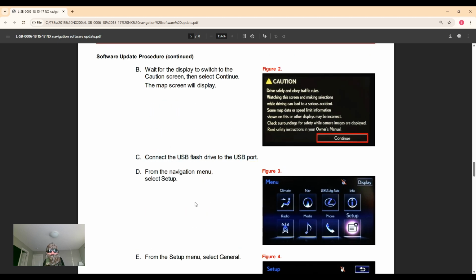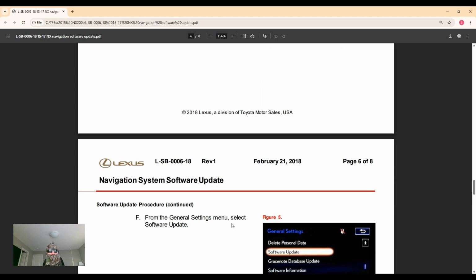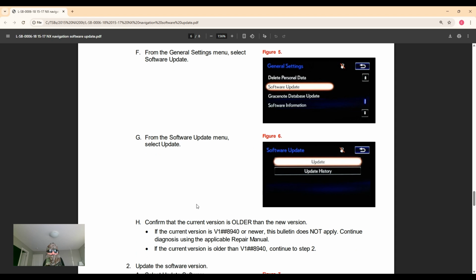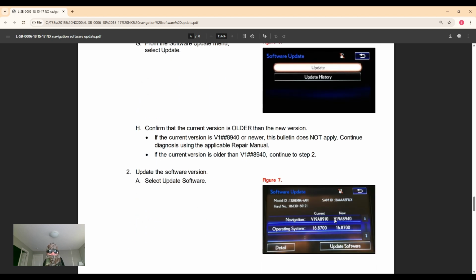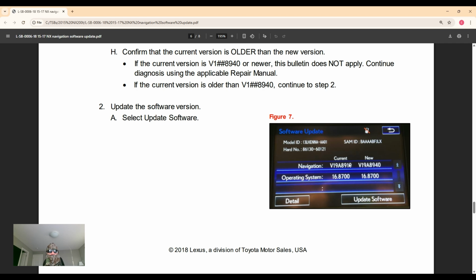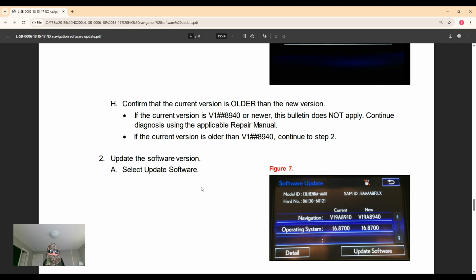So once they are in this main screen, they would connect the USB, then the setup, then general, then software update, and then it will show the current version and the new version. So the new version in this TSB is the 8940, and in this particular image, they're showing that the old one is 8910. If you already have the 8940, and you can check this yourself as well, you don't need to stick the USB in there to see what the current version is. So you can see if yours is one of the older ones, below 8940, then you definitely could get this software update done, but most likely you would have to pay for it.